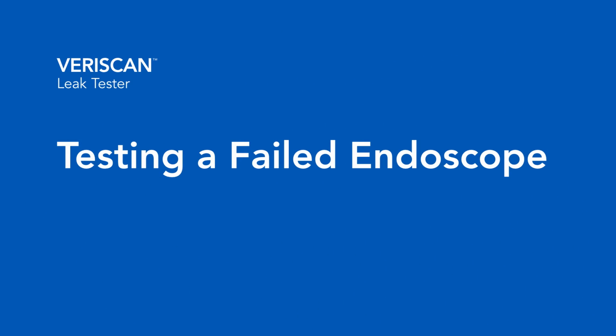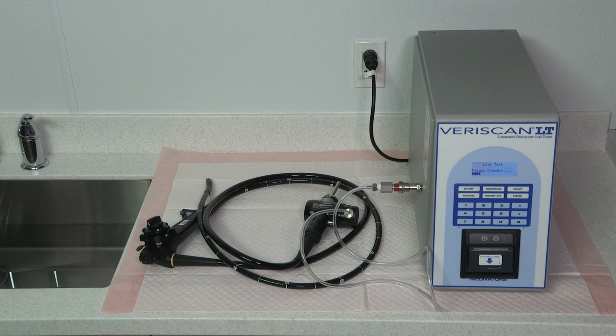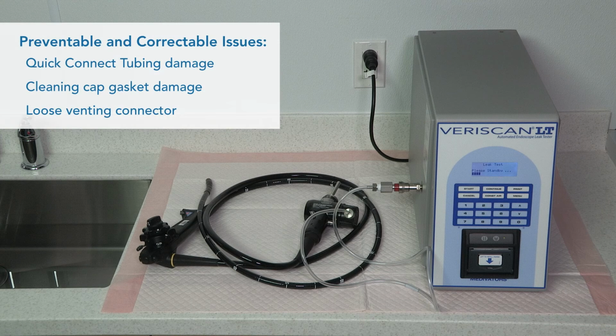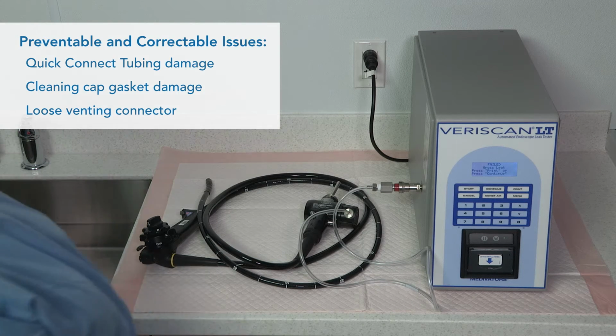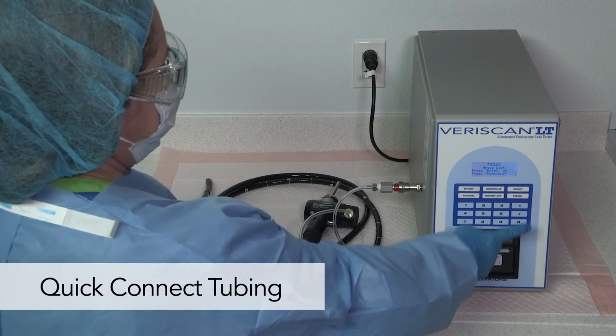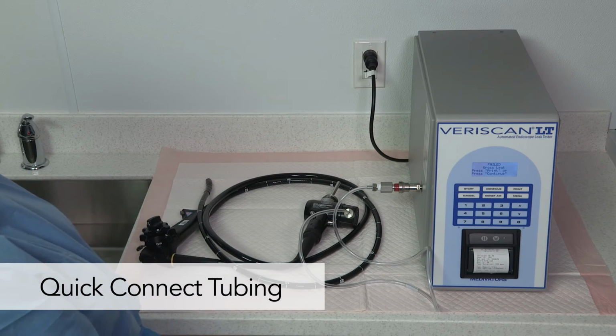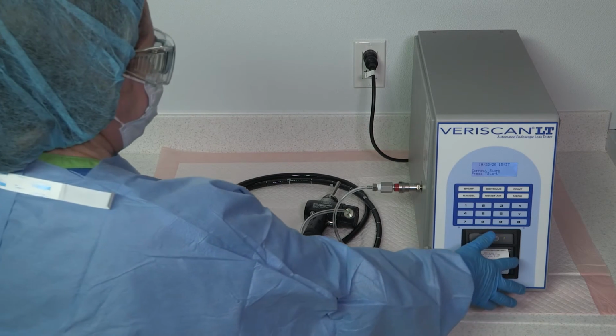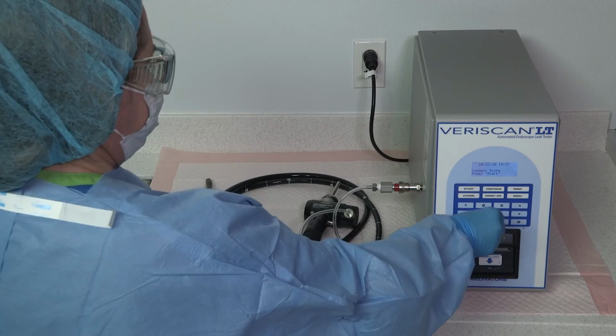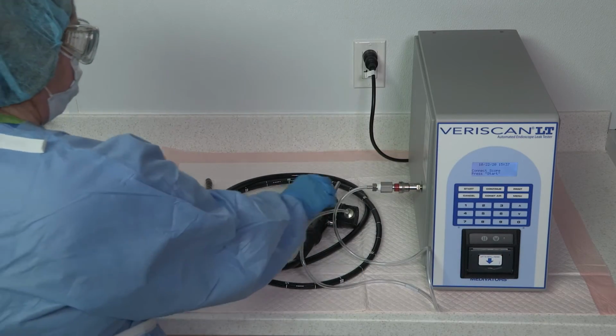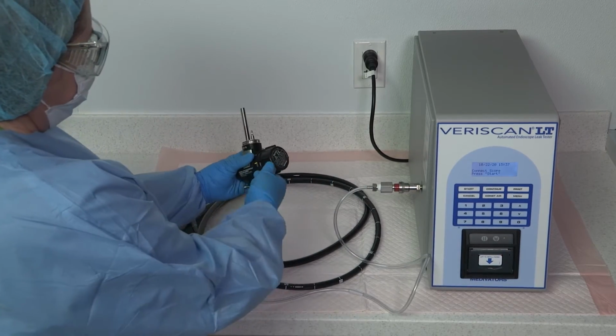Let's walk through what to do when an endoscope fails the first leak test. The majority of failed leak test results are due to true endoscope leaks. On occasion, a failed test result can be traced to several preventable and correctable issues. Let's review each of these. If the Quick Connect tubing is either damaged due to a small hole or worn due to an O-ring leak, a false fail leak test result can occur. Always have a spare Quick Connect tubing available to troubleshoot for a tubing leak.